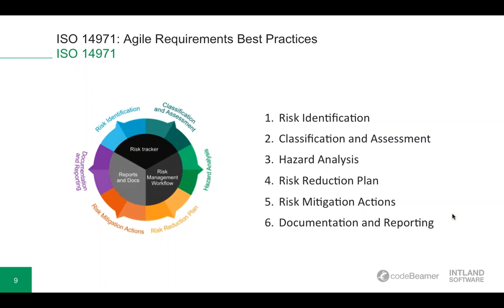First, identifying hazards and hazardous conditions associated with a medical device that could place patients or healthcare workers at risk. Then, estimating the potential occurrence of such risks and evaluating the extent of the consequences. Then, developing and implementing active safeguards within the device or the production process to control risks, and regularly reviewing and monitoring the process to assess the effectiveness of risk management controls and the risk management process. And I have this simplified here. You can see the steps here and in this chart as well.